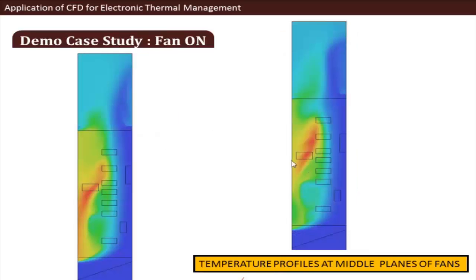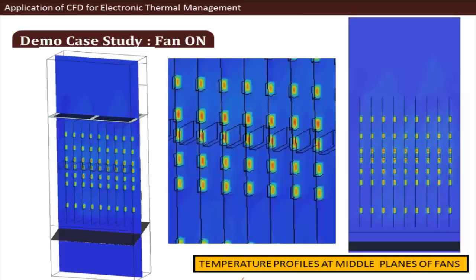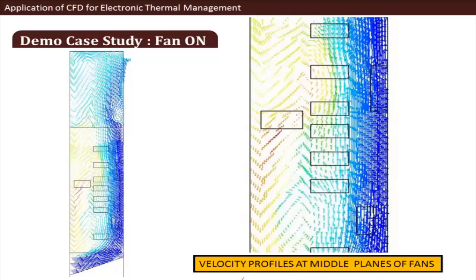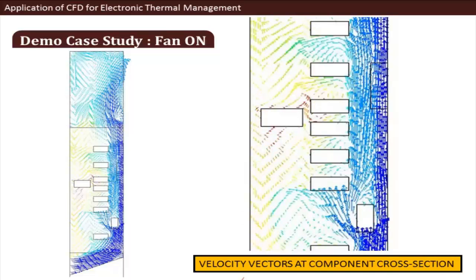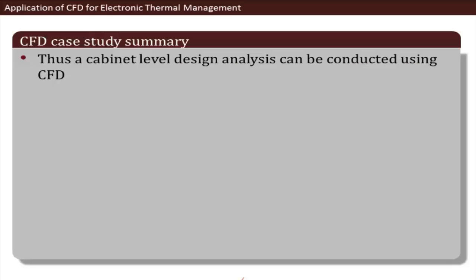There is still some flow imbalance — one side of the PCB heats up more than the other — but temperatures remain within operational range. Cut-section views show the temperature of each component, and vector plots confirm significantly higher air recirculation compared to the fans-off case. In summary, CFD has been applied to study a cabinet-level design, and similar analyses can be performed for device-level and board-level models.